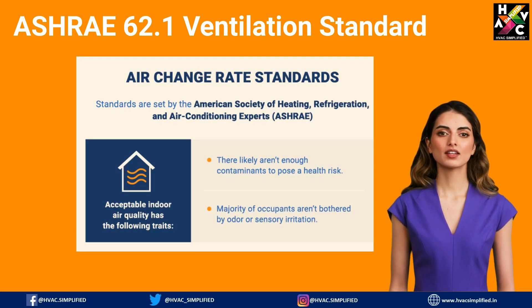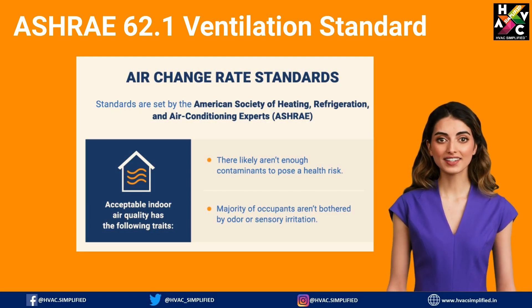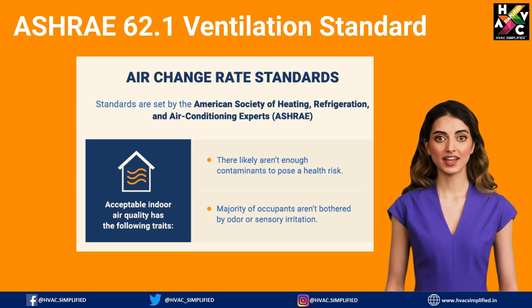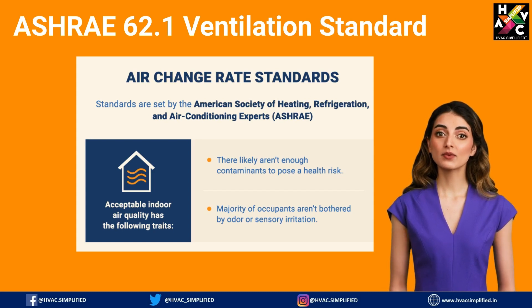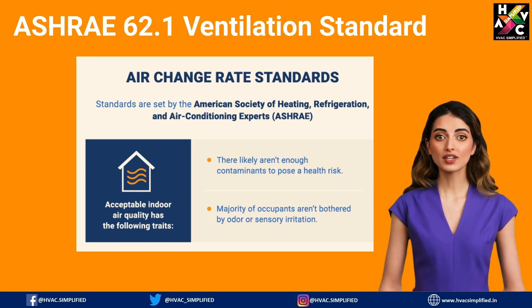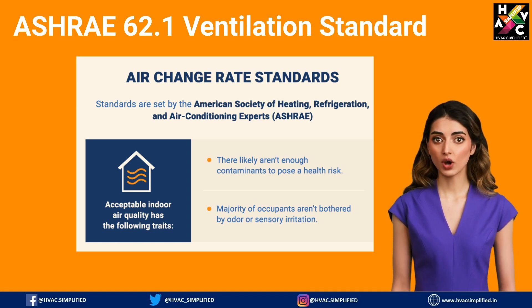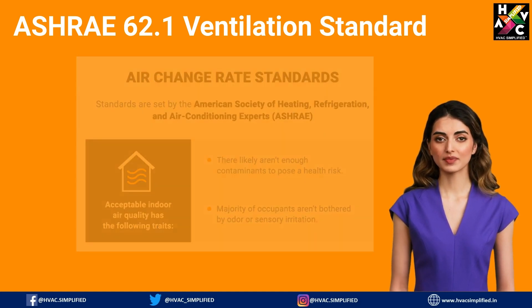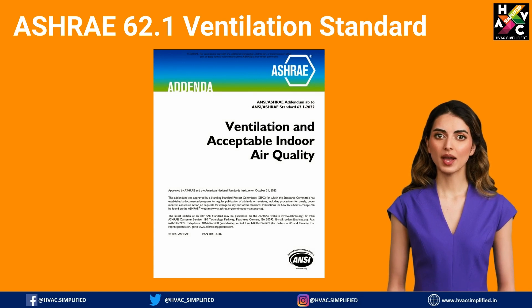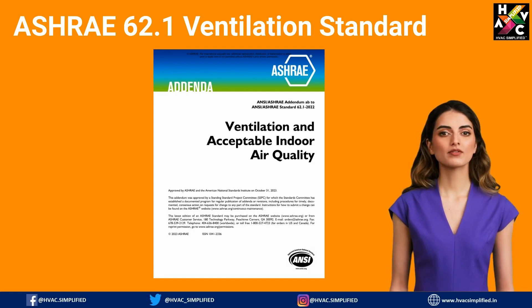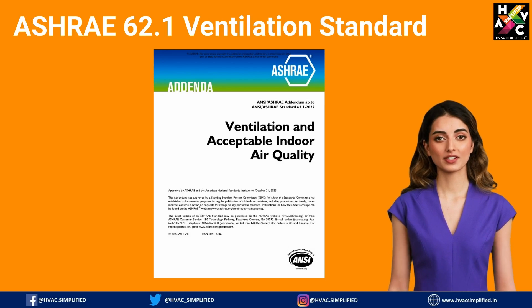ASHRAE — the American Society of Heating, Ventilation and Air Conditioning — sets ventilation standards in ASHRAE 62.1: Ventilation for Acceptable Indoor Air Quality. These standards define the minimum ventilation rates and indoor air quality levels for occupants in different building types. ASHRAE 62.1 uses the ventilation rate procedure to calculate outdoor airflow based on the number of occupants and space size, balancing energy efficiency with good indoor air quality.